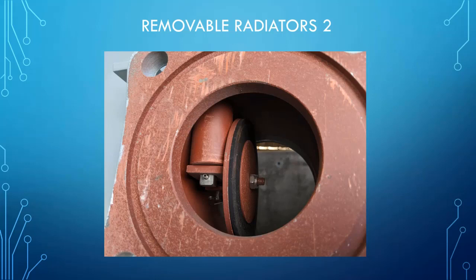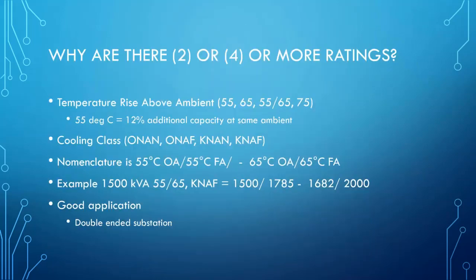I've seen consultants specify radiator valves on one side, on the tank side, and also sometimes on both sides. Obviously, the advantage to having them on both sides is you close both valves, remove the radiators, and you don't spill any fluid. If you only have the valves on the tank side, then you save all the fluid in the tank, but the fluid from the radiators obviously discharges onto the ground and must be dealt with. So this is a question I get all the time.